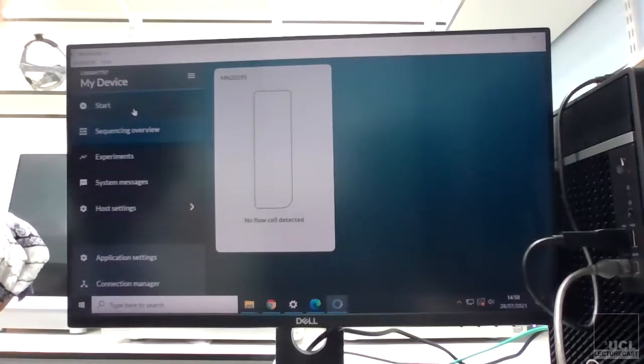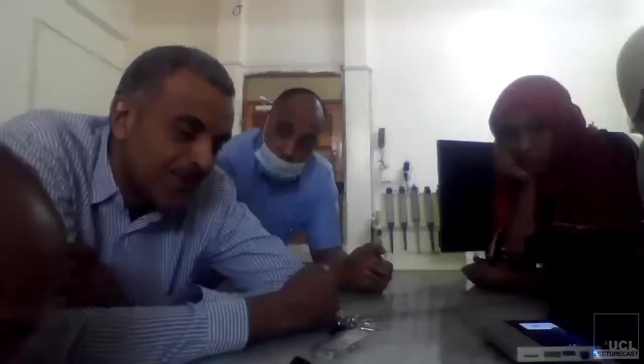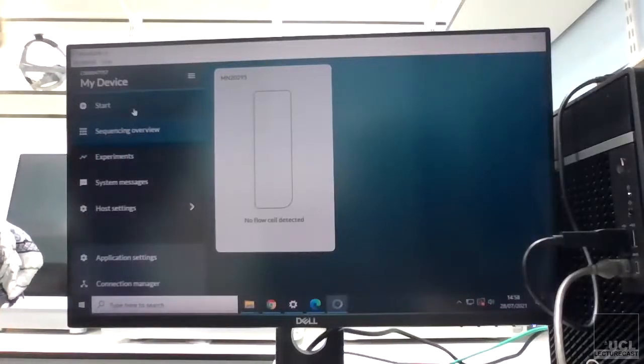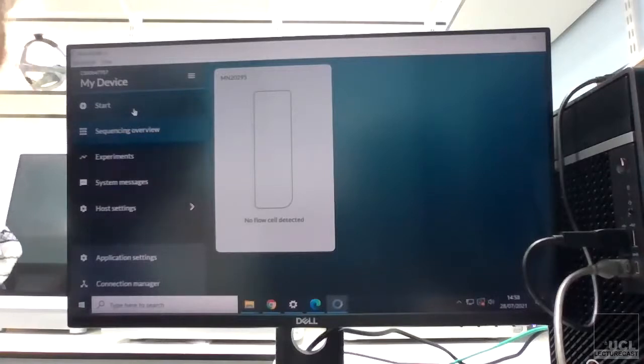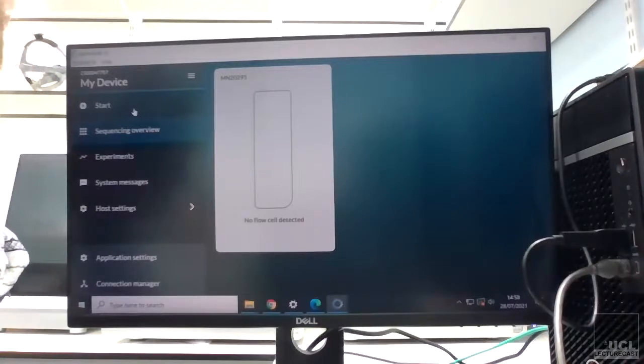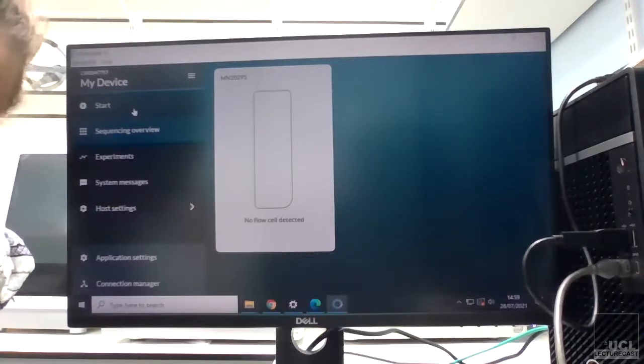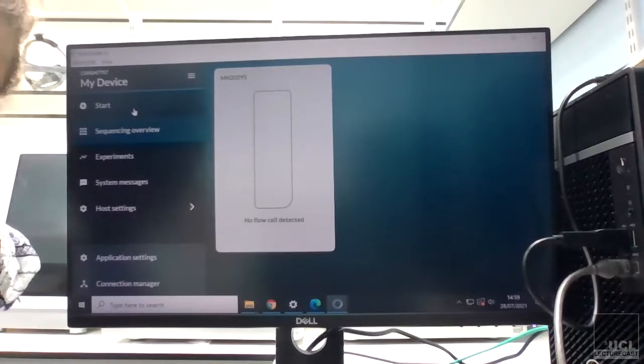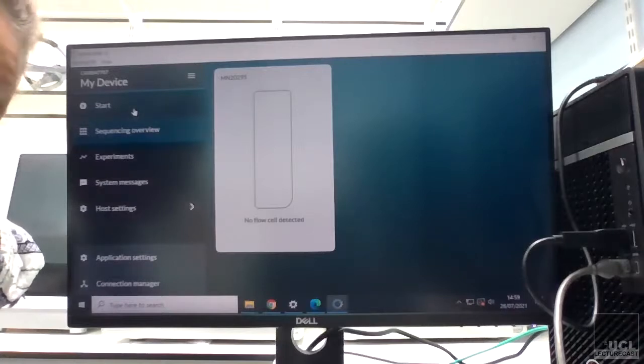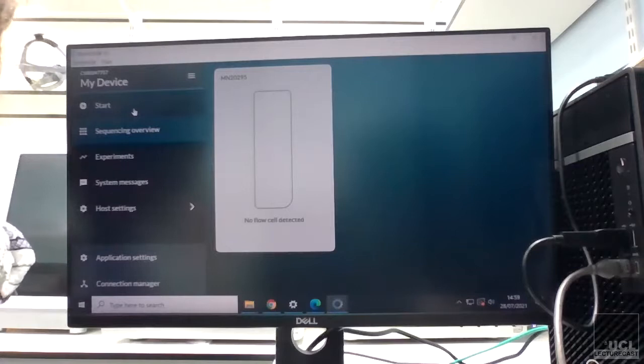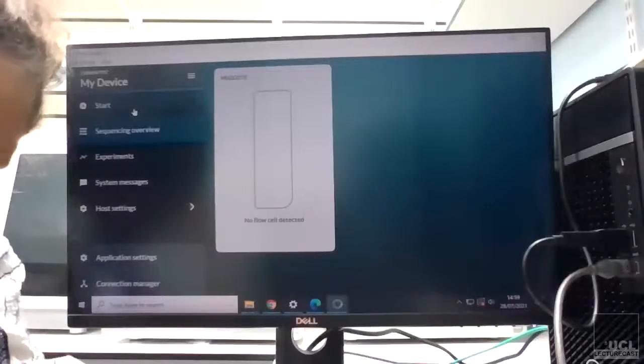So it's not useless, but definitely Nanopore should be replacing ones that are below 800. And I don't know what the policy is for getting them to different countries, but certainly in the UK, once you contact customer support, they're quite quick about it. Yeah, we'll just have to see. But I must admit the newer flow cells that we've been receiving are not as—they don't have as many active pores as the older ones that we've had. So I don't know whether it's a manufacturing issue or whether it's just the luck of the draw when you get them sent to you.